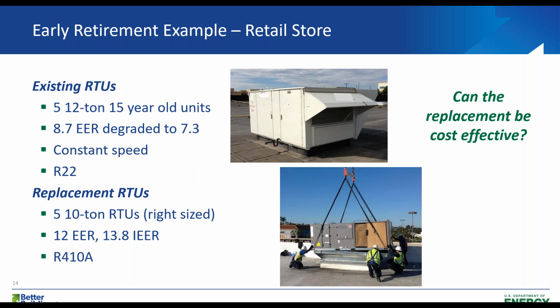Another thing you can find in the proactive business case is an example of early retirement that we created. This one's in a large retail store. So let's say this retail store has 5 12-ton, 15-year-old units. Each unit was at an 8.7 EER rating and has since degraded to 7.3. All of them are constant speed and have R22 refrigerants.